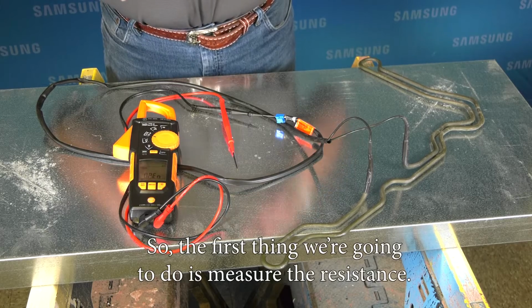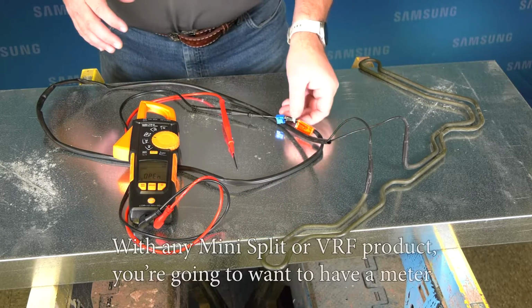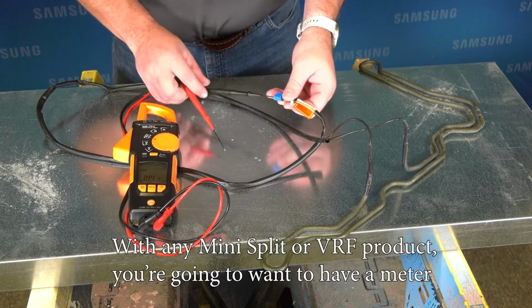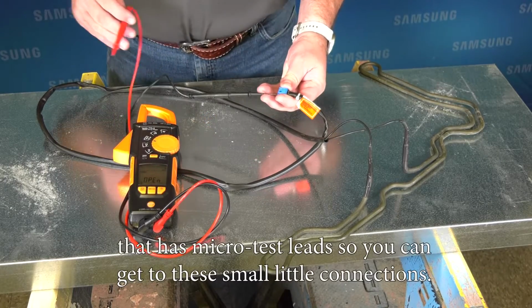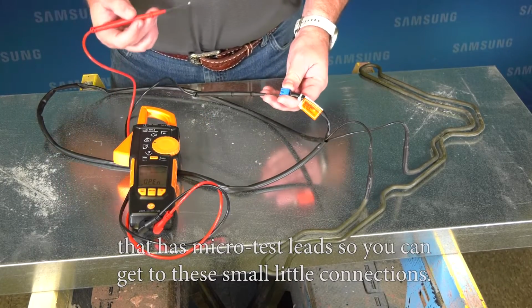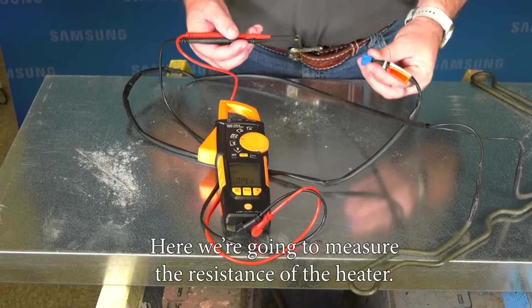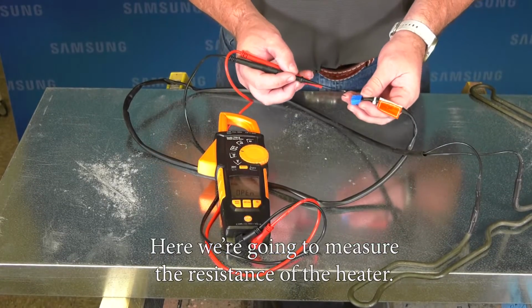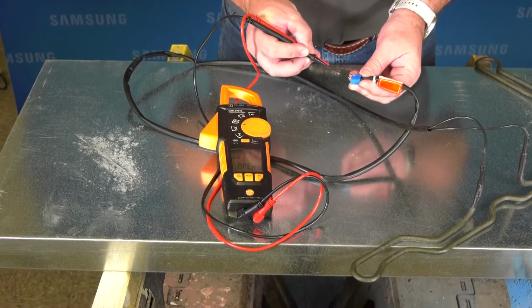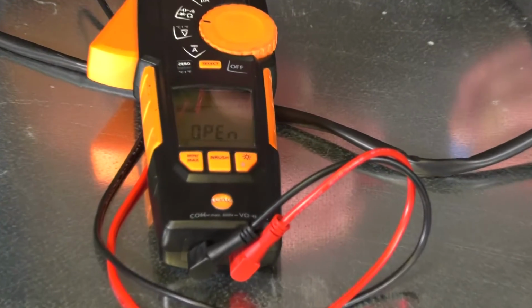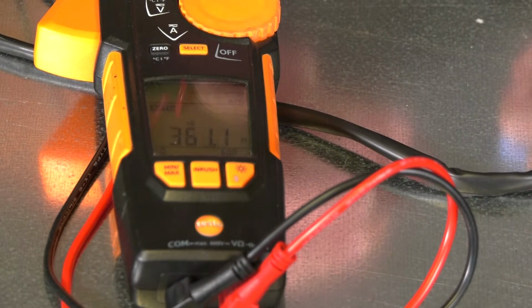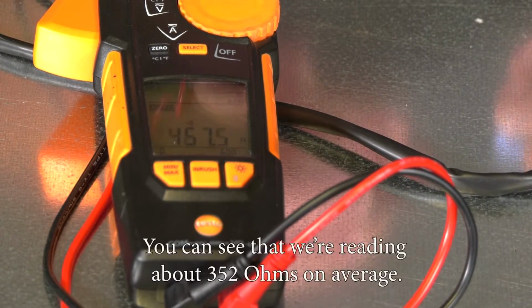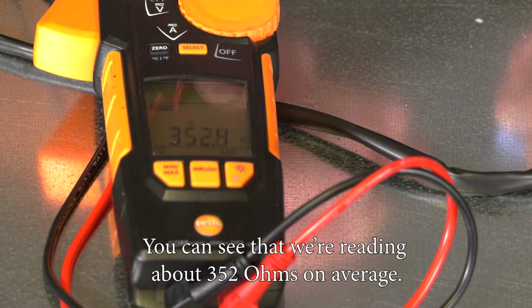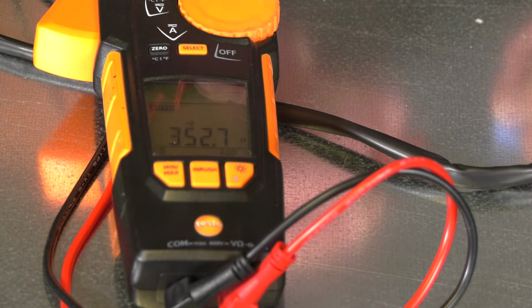So the first thing we're going to do is measure the resistance. With any mini split or VRF product, you're going to want to have a meter that has micro test leads so you can get to these small little connections. So here we're going to measure the resistance of the heater. And you can see we're reading about 352 ohms on average.